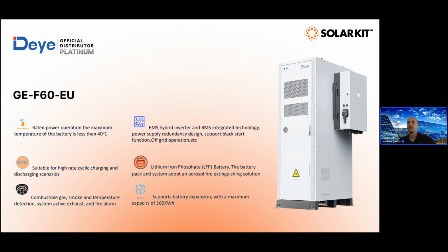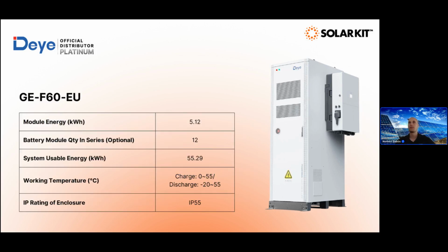You can connect 6 pieces of the batteries to one single inverter. So in total, you can order it with a 60 or a 50 kilowatt hybrid inverter. For one inverter, you can reach 360 kilowatt hour of capacity. And if that's not enough, then we will see the expansion later. Each battery module is 5.12 kilowatt hour. You have 12 of these inside one cabinet, and the maximum usable energy is roughly 55 kilowatt hour.